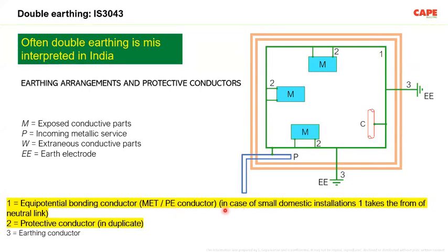Now, interestingly, in the IS standard from 1965 onwards, it is written that in case of a small domestic installation, one is taken from the neutral link. Sorry, there is a small mistake. One is taken from the neutral link. That means it's a TN-C-S system. So basically, what this picture says is, M stands for exposed conductive parts, meaning major three-phase electrical apparatus. These three-phase electrical apparatuses are protectively earthed to the equipotential bonding system of your building by duplicate connection. Number 2, protective conductor in duplicate. This is actually double earthing.